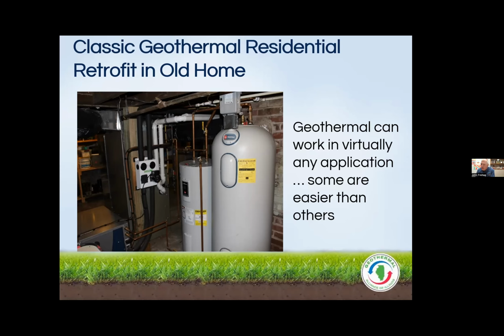You also see two water heaters, which is the classic geothermal desuperheater installation. The small water heater is the preheat tank—basically a tank with no heating elements that just preheats the water. The big water heater, a Marathon—I've got one just like it about five feet from where I'm sitting right now—is the water heater that serves the house.